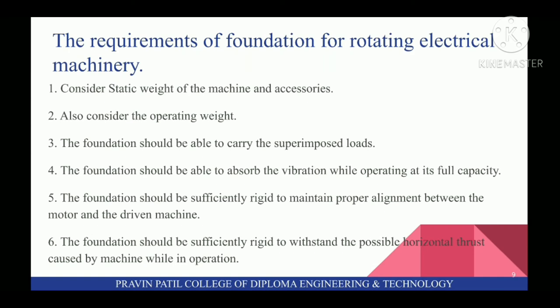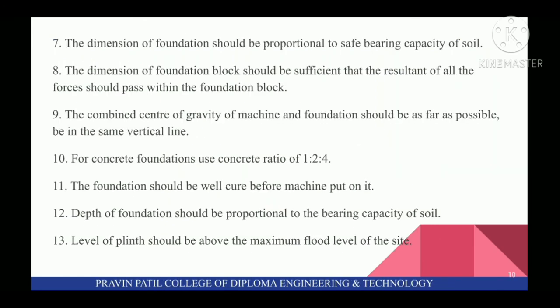Next topic is Requirements of Foundation for Rotating Electrical Machinery. First, consider Static Weight of the Machine and Accessories. Second, also consider the Operating Weight. Third, the Foundation should be able to carry the Superimposed Loads. Fourth, the Foundation should be able to absorb the vibration while operating at its full capacity. Fifth, the Foundation should be sufficiently rigid to maintain proper alignment between the motor and the driven machine. Sixth, the Foundation should be sufficiently rigid to withstand the possible horizontal thrust caused by the machine while in operation. Next, the Dimension of Foundation should be proportional to Safe Bearing Capacity of Soil. Eighth, the Dimension of Foundation Block should be sufficient that the resultant of all the forces should pass within the Foundation Block.